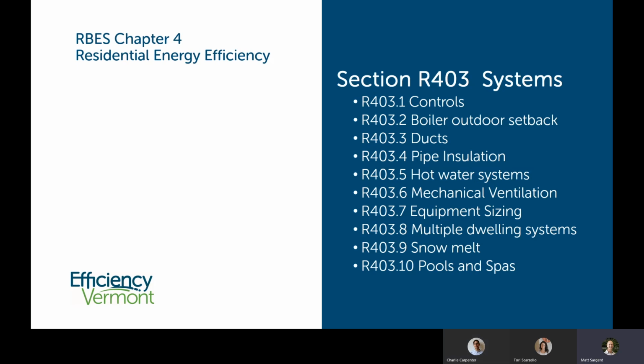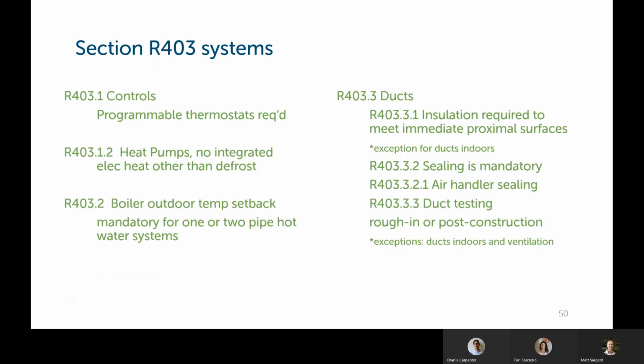Section 403 in the residential code discusses systems. So it gives us requirements for all these different systems, including controls, ventilation, hot water systems. All the stuff that's discussed in section R403. 403.1 requires programmable thermostats, and there are some exceptions to that. I think if you have a radiant heating system, there's an exception for that. In 403.1.2, heat pumps cannot have integrated electric heat other than the defrost mechanism. So we don't really see that in cold climate heat pumps pretty much anyway, but just to note that that provision is in there. R403.2 boiler outdoor temp setbacks are mandatory for 1 or 2 pipe hot water systems.